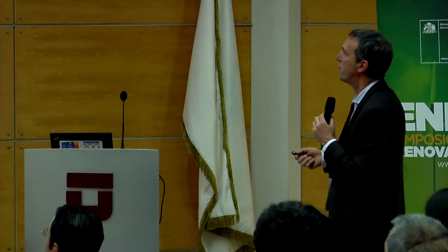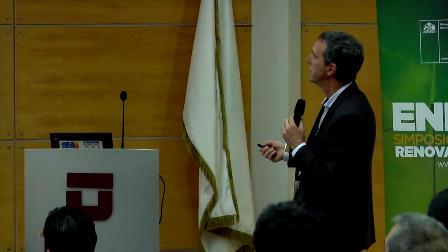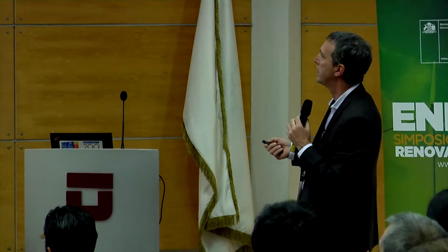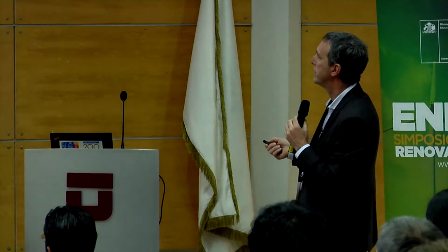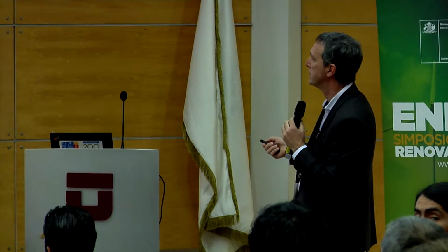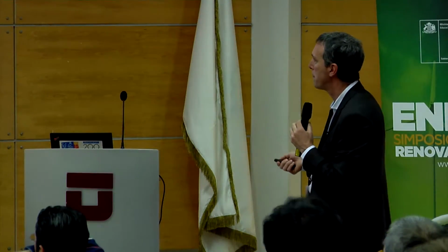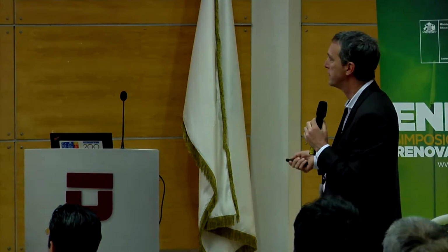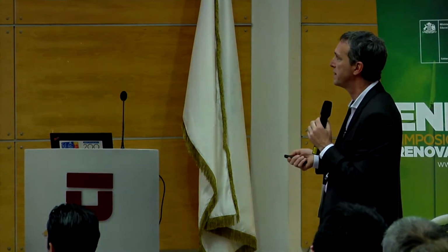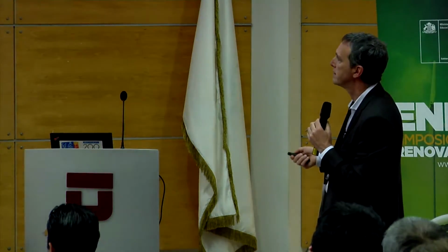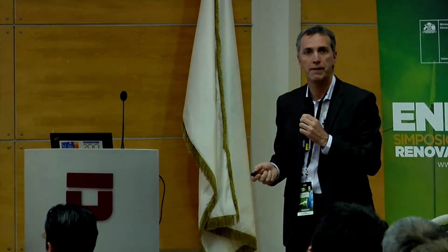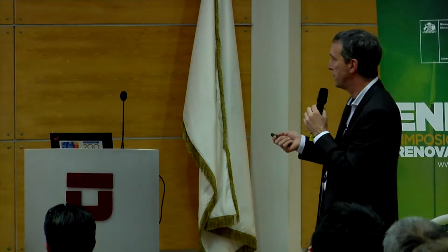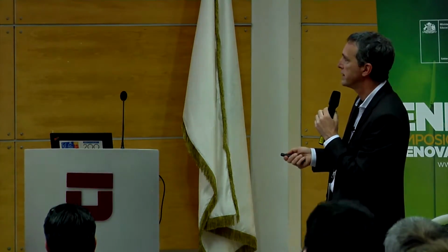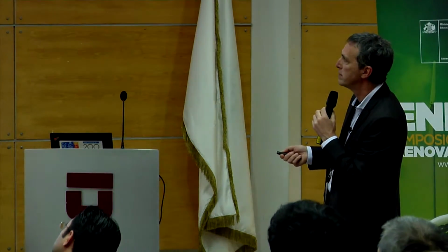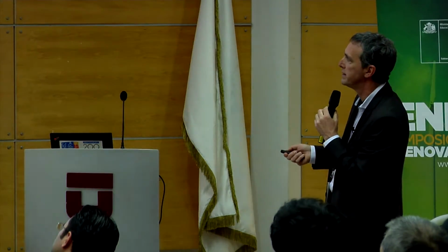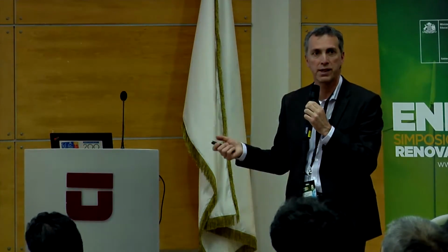This shows the 4-quadrant control on port 2. So you can see in port 2 negative active power and here plus and minus, positive and negative reactive power flow. Still in port 2 here, positive active power and then positive and negative reactive power. You can see on the basis of the phase shift of the quantities shown here. You can see that the current, of course, is multiplied by 10 in order to have a decent waveform to show together with the voltage.